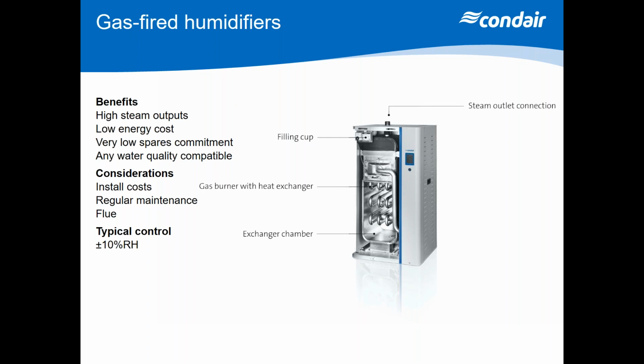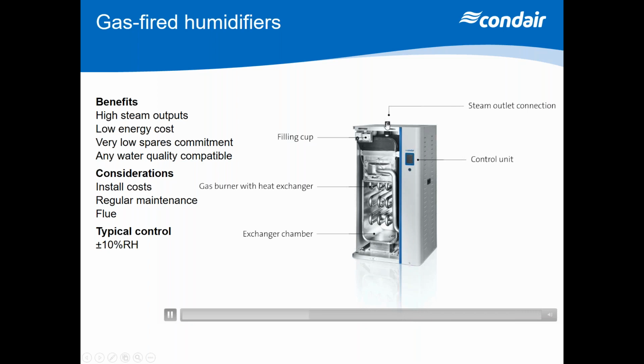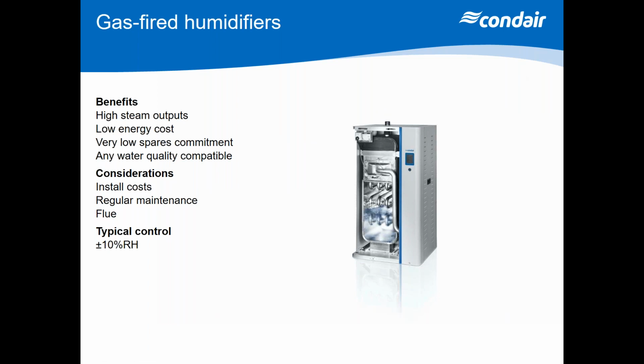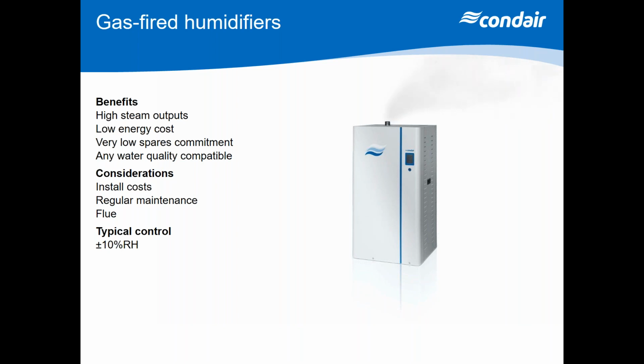Now, with all of these units, we're only producing steam at atmospheric pressure, so that reduces the length of the pipework that you can have between the humidifier and the duct, because the only thing that's driving the steam from these units is the expansion that happens as water changes its state from a liquid into a gas. That's what's driving it through that pipework. It's expanding by over 1,000 times. Of course, if you make that pipework too long, then that steam will start to collapse and you'll lose your duty.